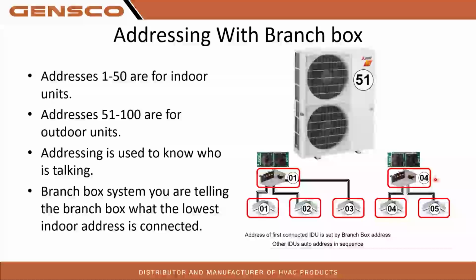If you do have multiple branch boxes on your system, again, your first branch box, always your first branch box, you should be addressing it as 0, 1 because that's where your first indoor head is going to be. If you have a second branch box and you want to know how to address that, count how many heads are on your first branch box. In this example here, there's 3 indoor heads on this branch box, plus 1 more. So now address 4 is on this branch box. This branch box now becomes address 4. So what we just did, we told it, hey, the lowest address connected to you is address 4. So it starts automatically addressing everything from there on. And now the system knows that address 4 is on a separate branch box and knows where to send refrigerant to and which valves to control.